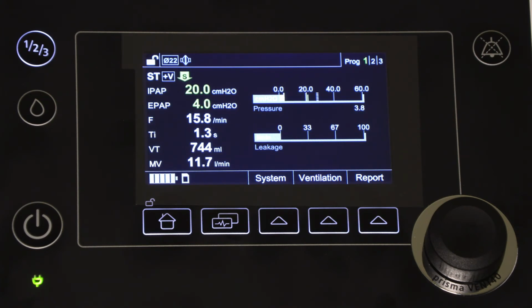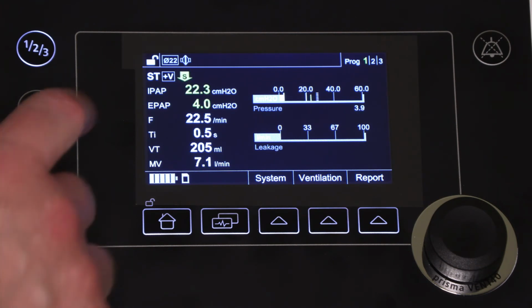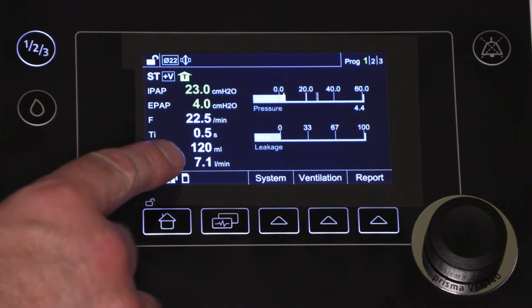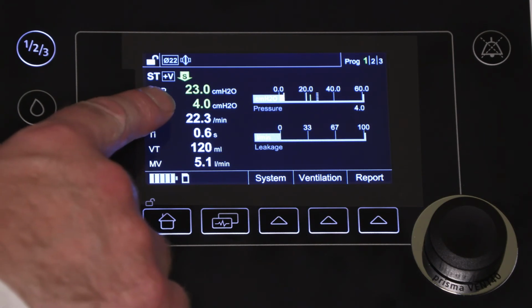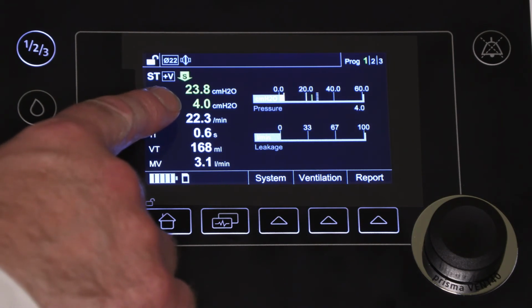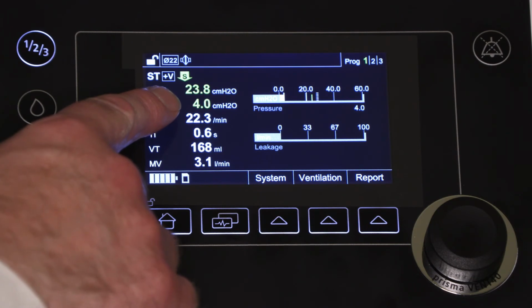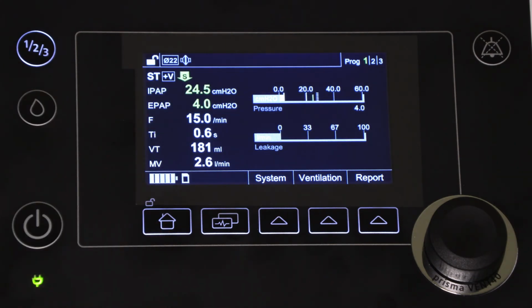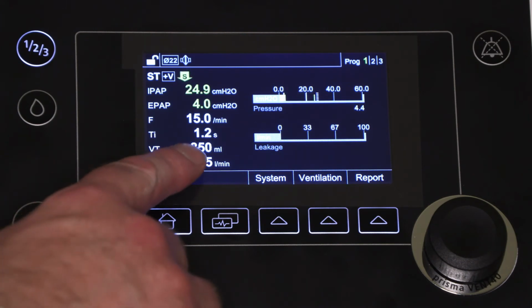Note the patient's IPAP setting and volume on the left side of the screen. We've got target volume turned on with a target set of 400 millilitres, and we've enabled the device to give a further 8 centimetres of IPAP if it needs to. Let's see what happens when the user's tidal volume becomes compromised. Note that the tidal volume is now dropped below 400 millilitres, and this has been picked up by the ventilator. As you can see, the IPAP is now starting to increase and keeps increasing. Once the user's tidal volume has gotten back to 400 millilitres or higher, the IPAP stops increasing as the tidal volume has reached its target.